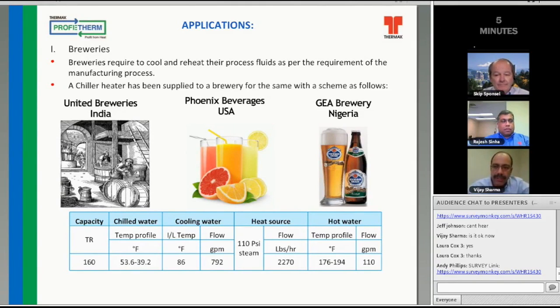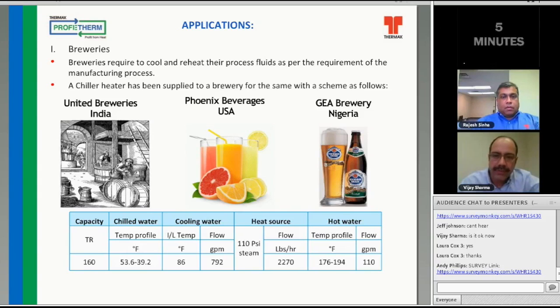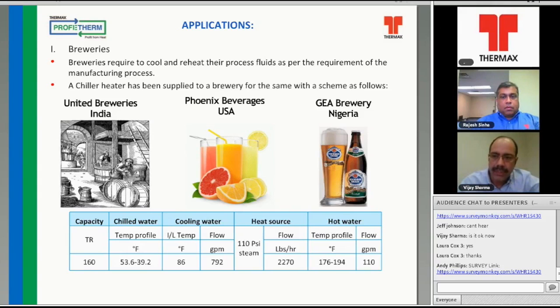Thank you. Yeah. So breweries is the one, again, an application that we have been doing in United Breweries in India, Phoenix Beverages, this is in USA, then GEA Brewery in Nigeria. So the capacity and the temperature ranges you can see here, we are going up to 39.2, which is the lowest cooling water temperature, and the heat source used is steam. The steam is used at 110 pounds, and then the hot water temperatures that we are giving to the application are 176 and 194.